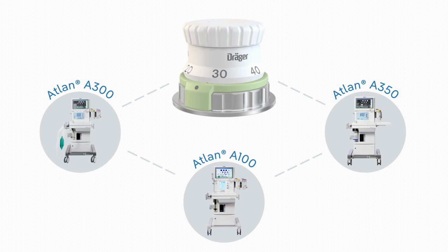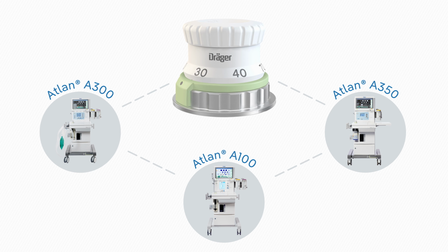All Atlan family devices use the same APL valve, which delivers a linear pressure pattern and thus reliably prevents excessive pressures in manual ventilation.